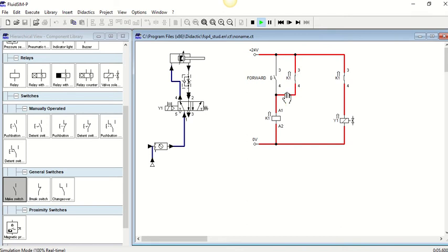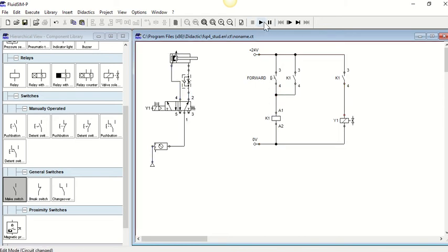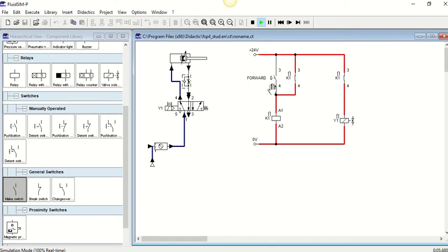Now the only way K1 can come on is if we energize it through the forward. This can only come on when forward is pressed. So hopefully that makes sense that it can actually only go on this loop. But you will see once that comes on, K1 has closed over, so it is able to keep power just going through here. And that is what we call a latch. Even after I take my finger off that forward button, it is now getting the pathway through these two.